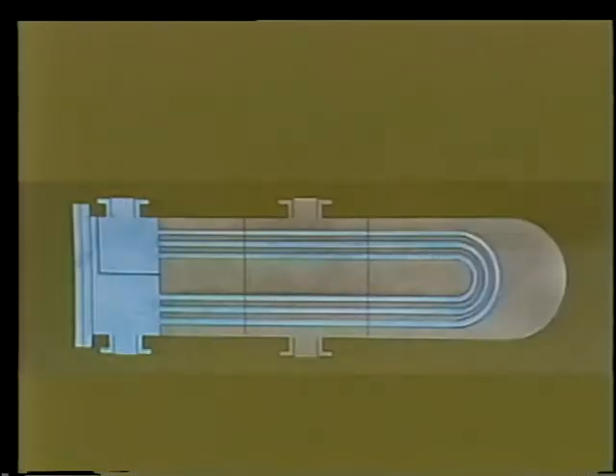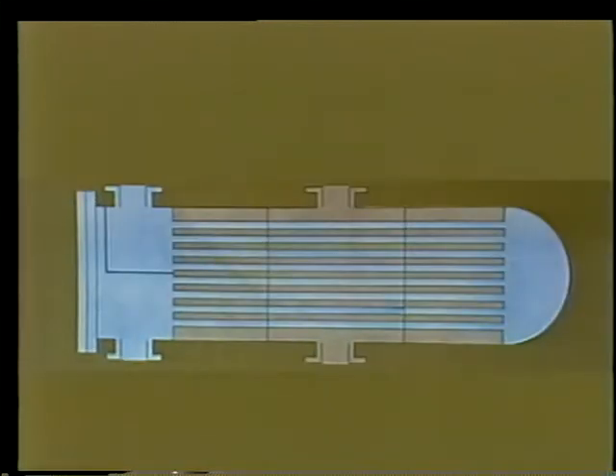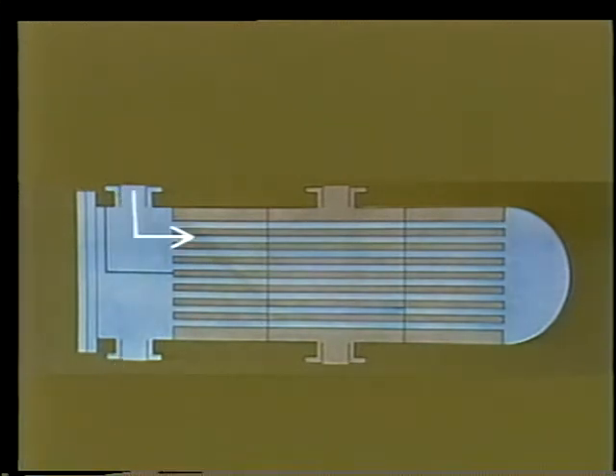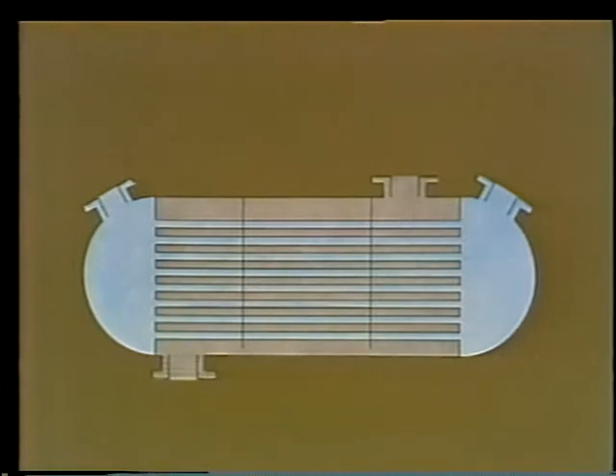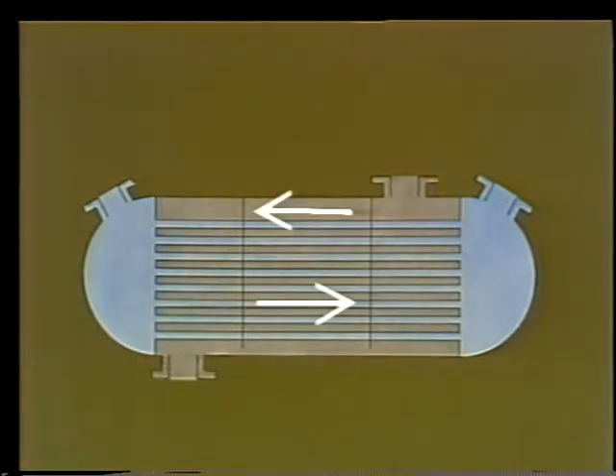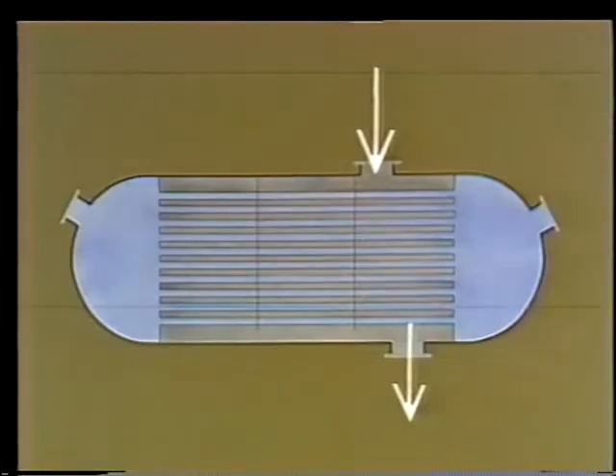The tube arrangement may be straight tube or U-tube. A straight tube exchanger might be a multi-pass unit if the head at one end is divided into two water boxes, one for inlet and one for outlet. The flow through a shell and tube exchanger with a straight tube single pass arrangement can be parallel flow, reverse flow called counter flow, or cross flow.